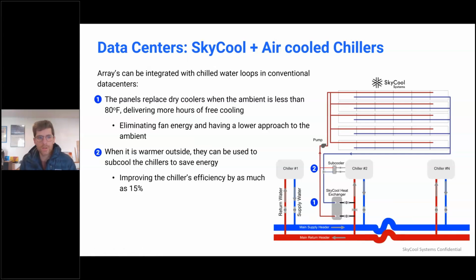In data centers, there's a slightly different integration that we would present. We haven't done this in the field, but I'll talk about the data center case study that we made. It's more modeled than actually built. But the idea in data centers is there's an opportunity to improve the efficiency of the chillers in the hot times of the year by subcooling, and then in the cooler times you can use the panels as essentially free cooling. And it would essentially replace a dry cooler, which is essentially a way to use ambient air to cool a chilled water loop. But instead of using a dry cooler with fans and a pump, we would just use our panels to directly cool the chilled water loop.